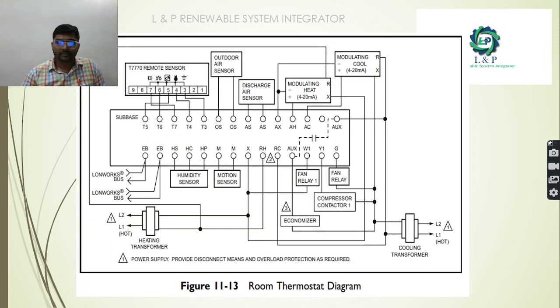Okay, so this is the room thermostat diagram. As you can see here, we have a 4 to 20 milliamps output command for the modulating, especially whether it is for heating or cooling, we can command using the 4 to 20 milliamps output from the controllers. So we have the sensors to monitor the humidity, and we also have the sensor to monitor the motion, that is the occupancy. Okay, and most importantly, in order to control the fan relays, we are providing the transformers and power supplies. Okay, in order to measure the outdoor air, we have the outdoor air sensors also.